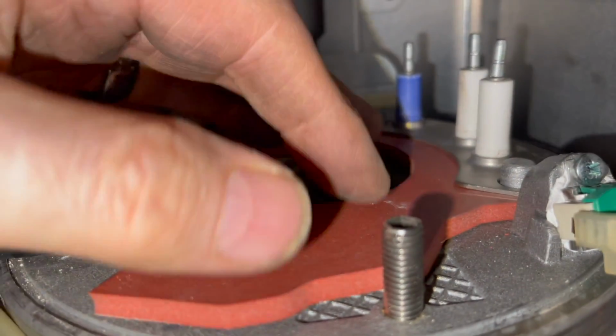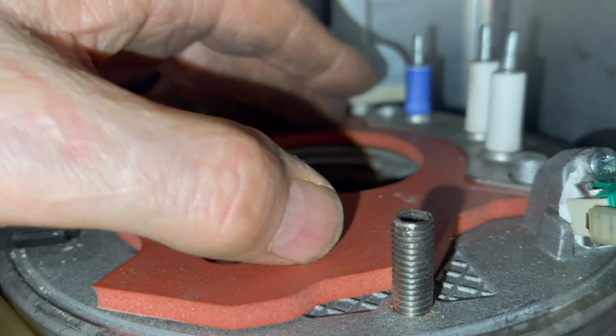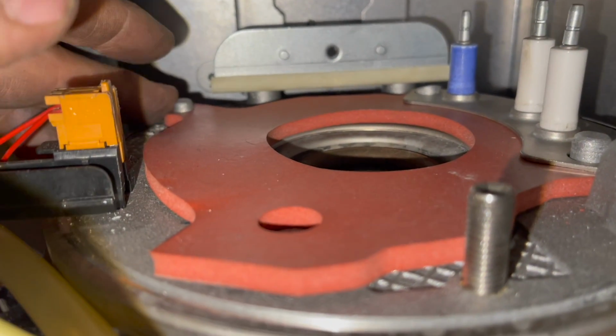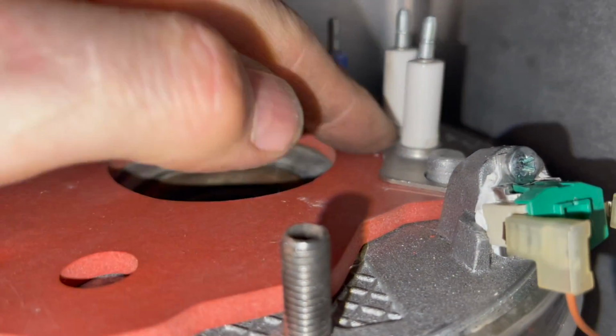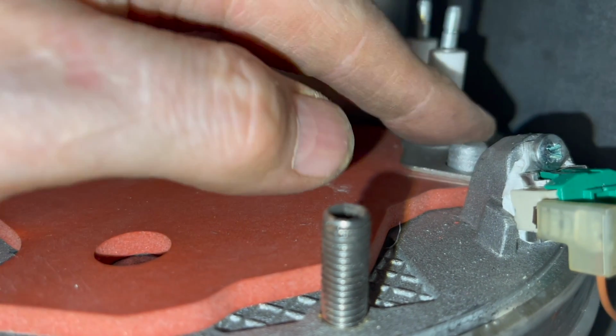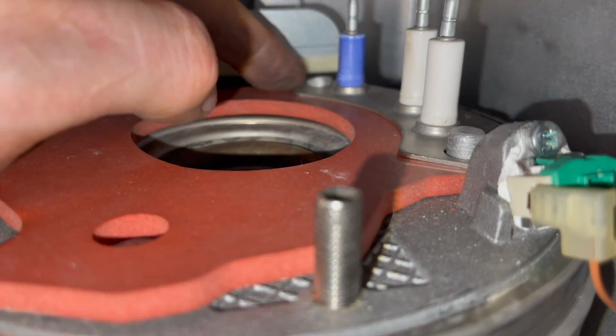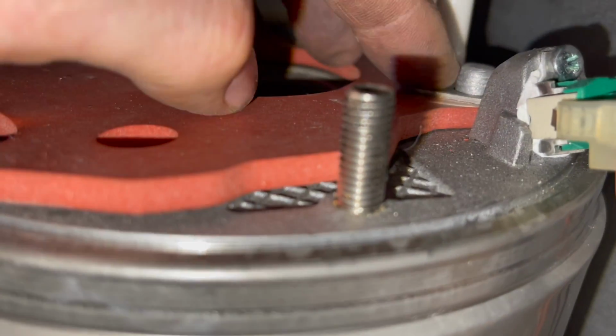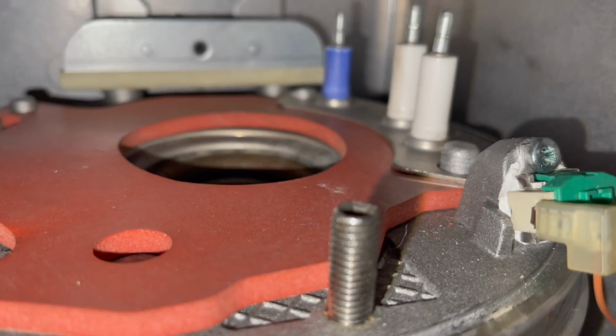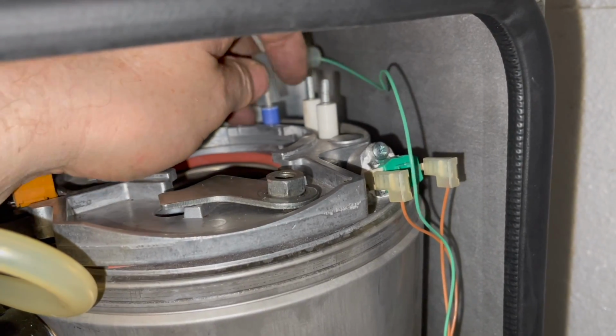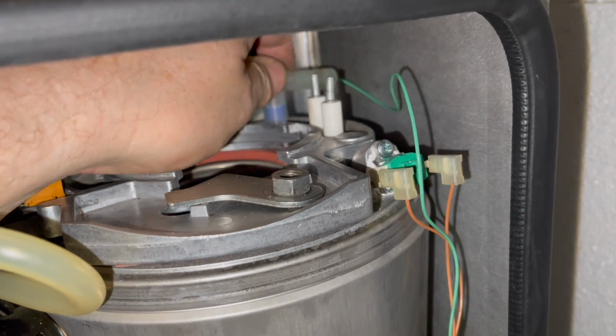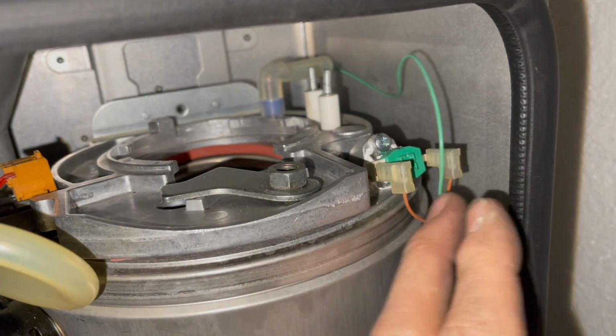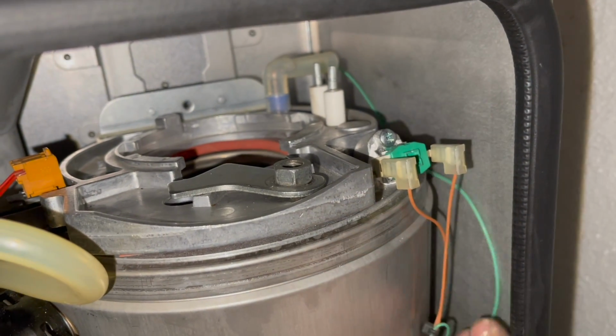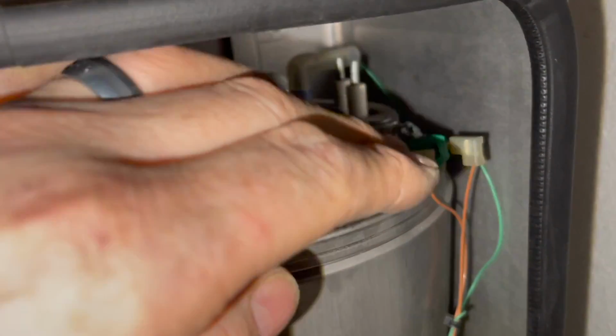And obviously the gasket will only go in one way. So you can see it locates on there. And the electrodes go onto those little clamps there. So you can't get that wrong. Now what I do before I put the fan back in is make sure the electrode leads go back in, because if you don't put them in, it will be an absolute nightmare to try and get them back on.